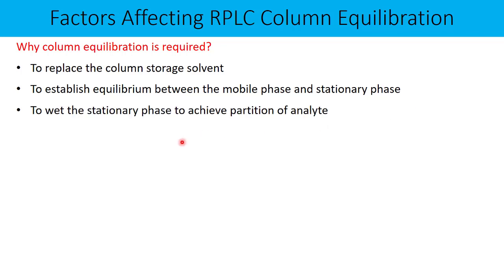The third point is very interesting and important: to wet the stationary phase to achieve partition of the analyte. In reverse phase liquid chromatography, our column is naturally hydrophobic or nonpolar. If our mobile phase doesn't wet the hydrophobic stationary phase, our analyte cannot reach the active sites present on the bonded stationary phase like C8 or C18. So the entire bonded phase has to be properly wetted, and this is possible by proper column equilibration with the mobile phase.